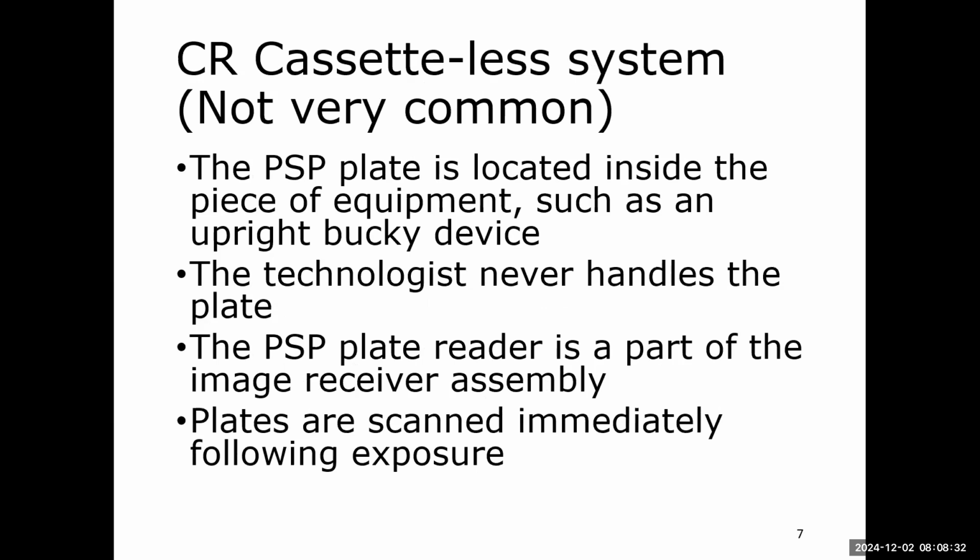Again, I never saw this type of system where the PSP plate was located inside of the piece of equipment, such as an upright Bucky device. The technologist there wasn't a cassette or a plate to handle. So I never actually saw this, but the PSP plate was built into it. It was a part of the image receiver assembly, and the plates were scanned within the equipment.